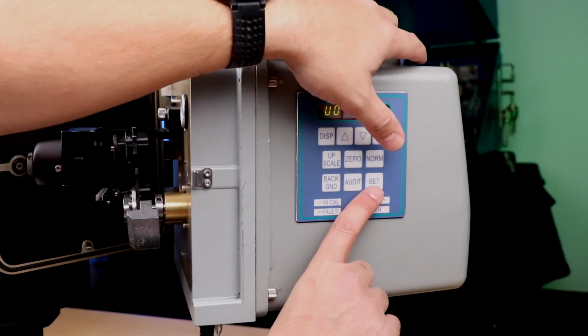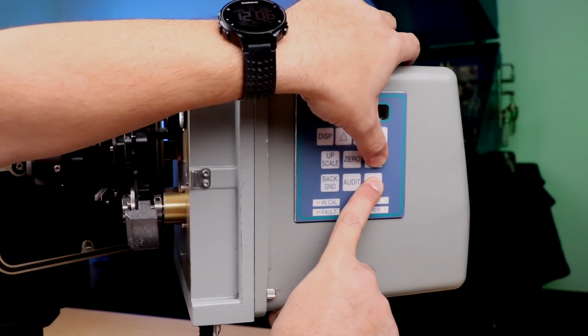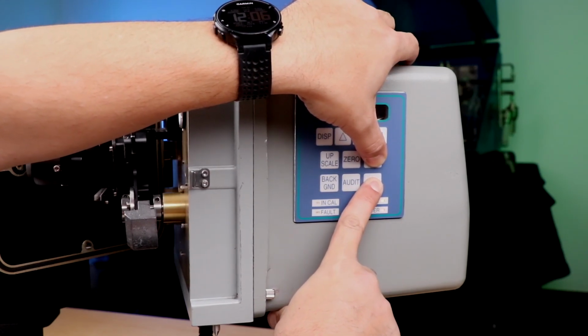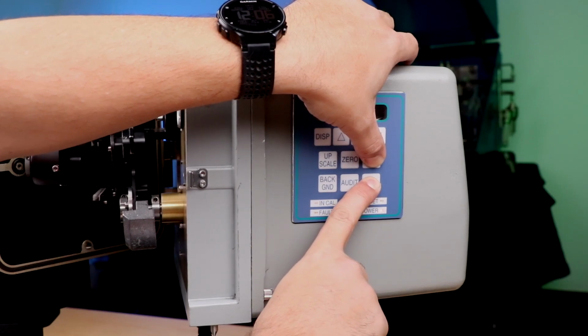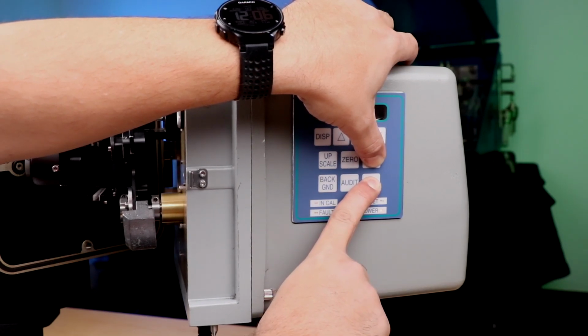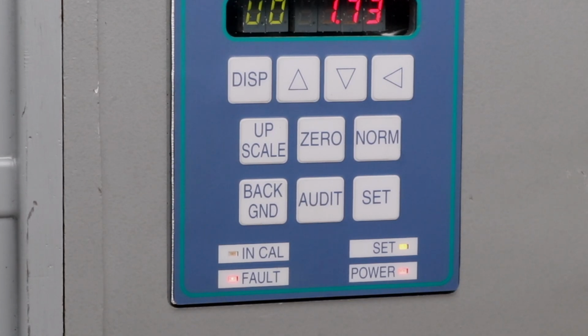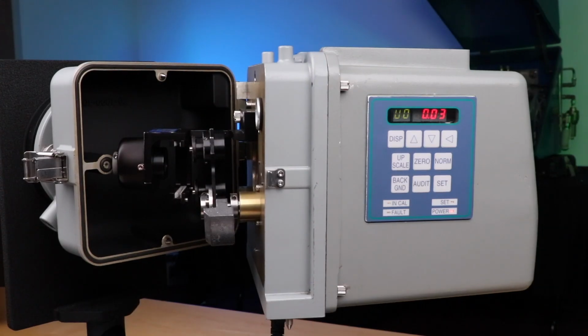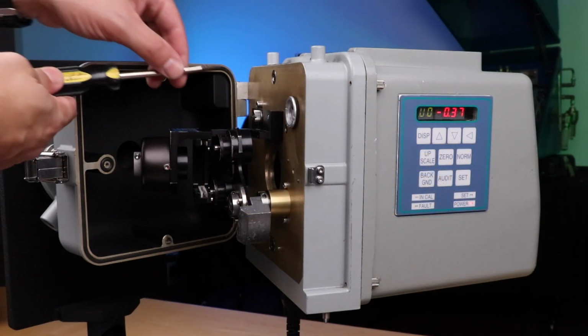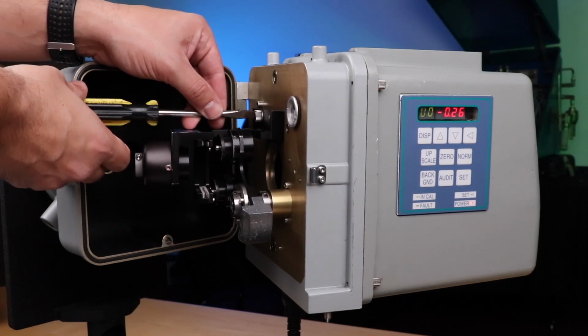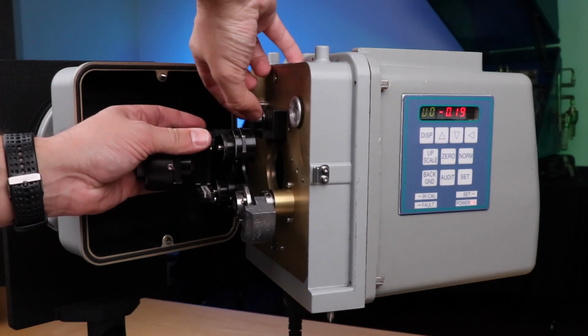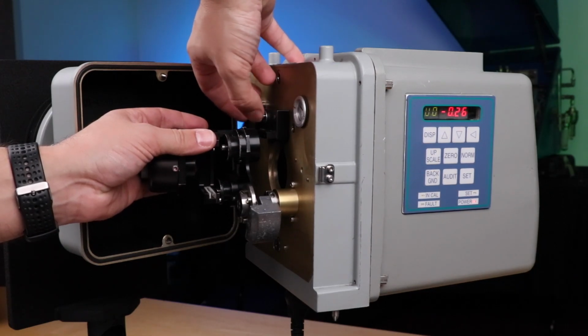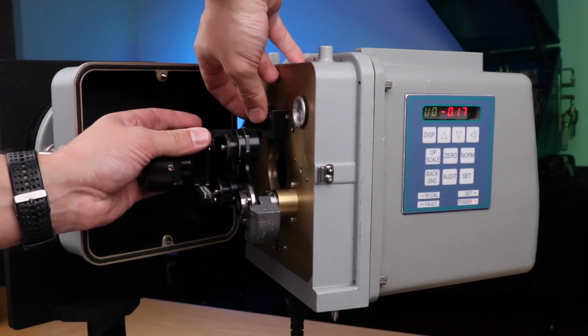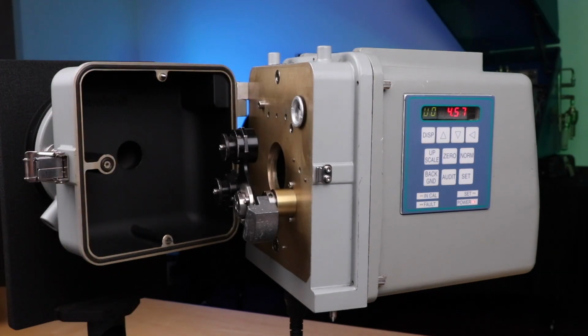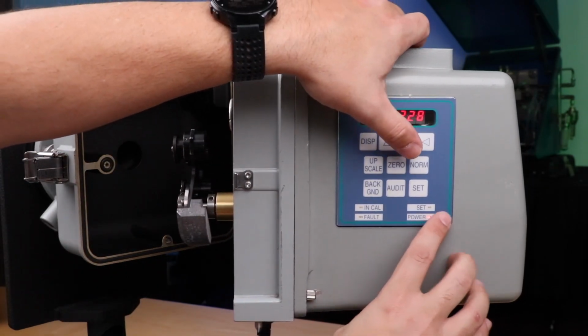With the blocking plate removed, you can now initiate the normal set. Do this by holding Set and Normal buttons for about 6 seconds or until the set light goes solid. The normal set can also take up to 6 minutes to complete. Do not disturb the unit during this process, as the ClearPath current reference values are being re-established. Once the normal set is complete and the set light is out, you can now perform the zero set. For this last set, you should remove the cal fixture. Initiate the zero set by holding Set and Zero until the set light is continuously illuminated.